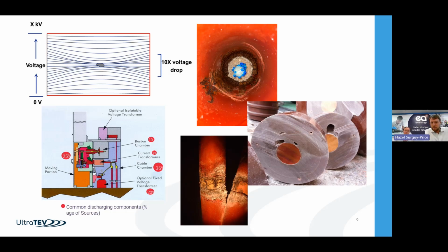The next picture, just slightly below, is an internal void. You can see how the insulation is meant to be consistent all the way through, but has now got these big air voids inside where it's started to break away and eat at the insulation.